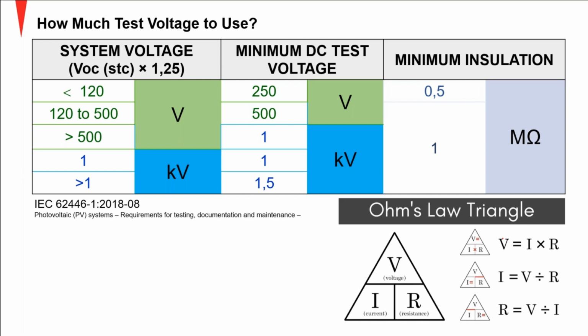Well, because we are talking about photovoltaic systems, this table only goes up to a certain voltage. And typically, if you have a system below 500 volts, you go with a voltage that is above that nominal voltage. So if you have 120 volts or less as the nominal voltage of the system, you want to test with 250. Somewhere in between 120 to 500, the maximum voltage to apply is 500. If you have a system that operates above 500 volts, then you want to use 1 kilovolt.